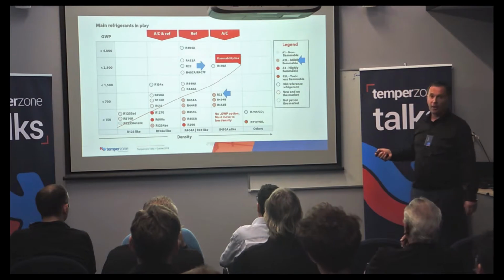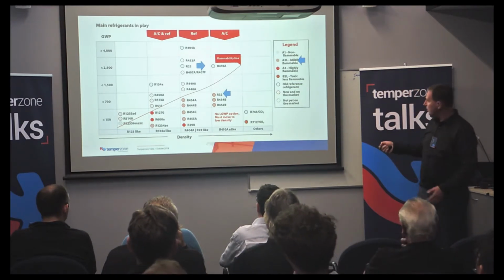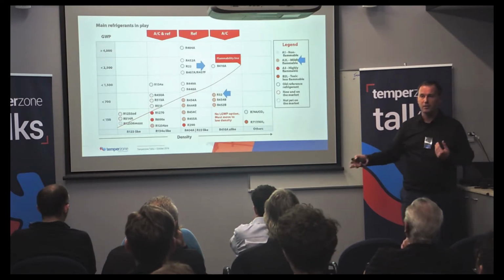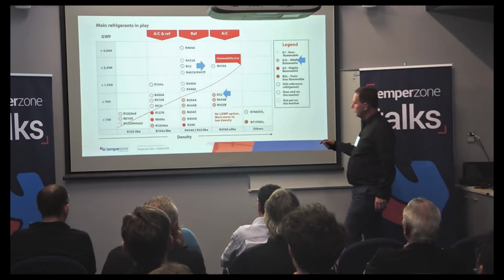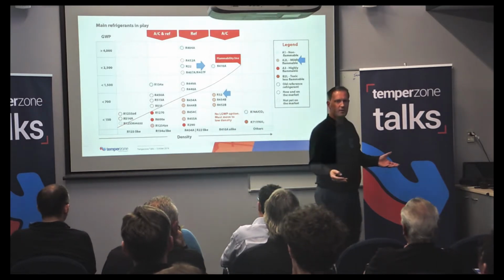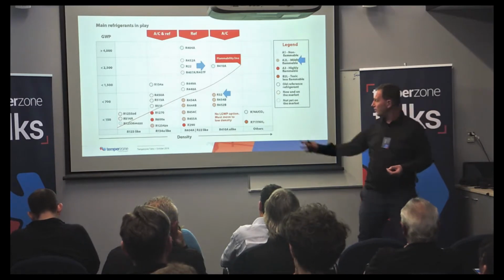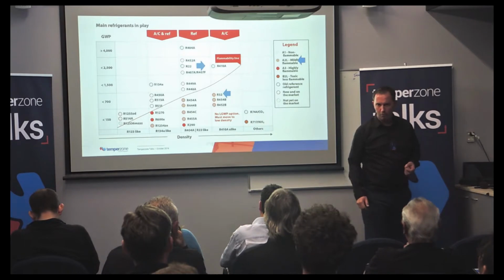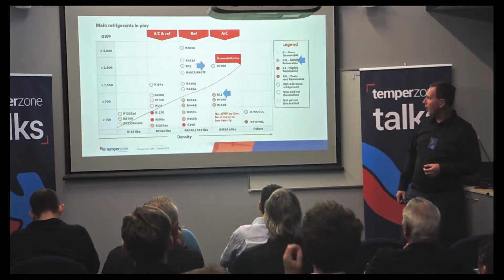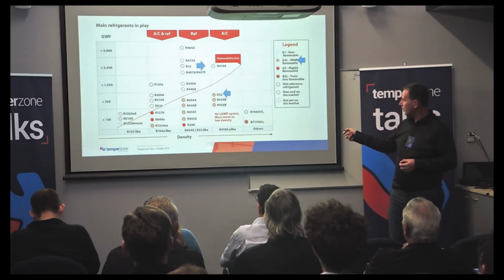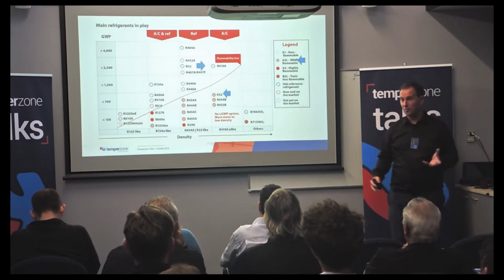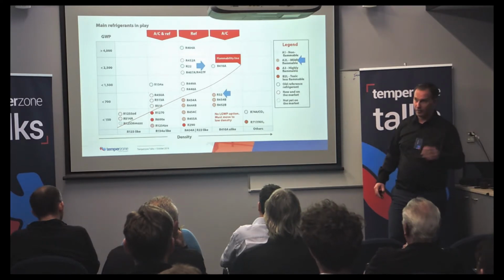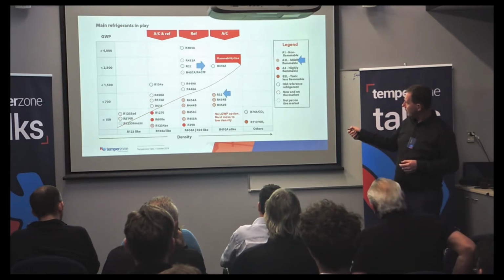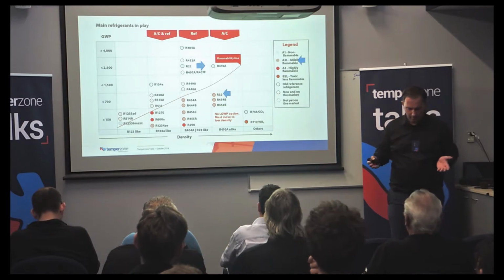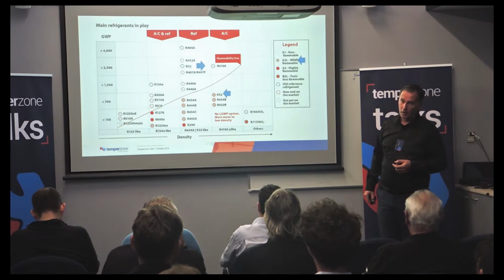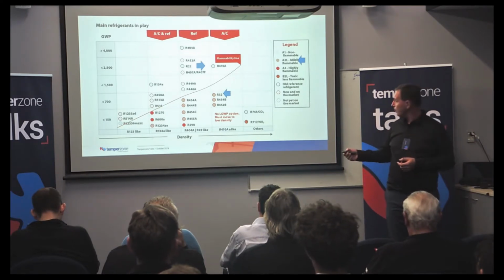And if you look at why we chose R32, residential products have gone to R32 largely already, and we're just starting the process of converting commercial products. As you go to the left on this graph, units have to become bigger per kilowatt of cooling that you deliver, and as you go to the right, they become smaller and more compact. As you go up, you get increasing GWP, and the line in the middle separates flammable, explosive and toxic ones from non-flammable ones. So we've taken R410A, and R32 is exactly 50% of it. It's got a GWP of 675 versus 2000 for R410A.